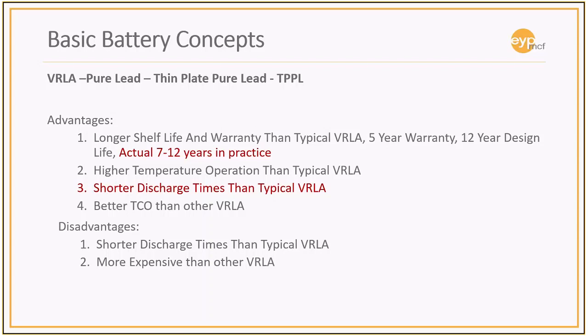So designing to 15 or 20 minutes of battery isn't necessarily their target, and they're looking for somewhere between 5 and 7 minutes or even a little shorter. These pure lead thin plate batteries are a good alternative to that short time to make sure that you've got your coverage. The disadvantage is shorter discharge times than a typical valve regulated battery, but you're designing to that. They're a little bit more expensive than the valve regulated battery because you're getting a little bit more of a warranty on them. They're a little bit longer life, and you're able to get that shorter discharge time.